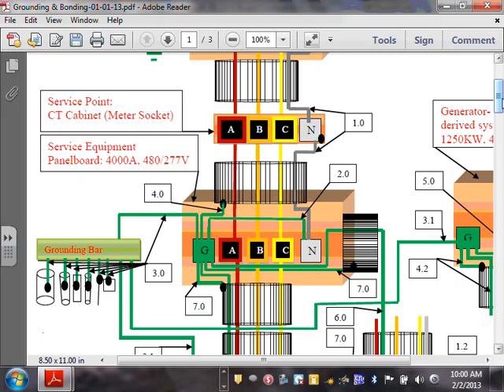And I take my neutral and bond it with that green, till you see that little number 2, and I bond the neutral. You do this at every service if the service is a grounded system. If the service is an ungrounded system, that number 2 does not exist, right? Any comment, any questions about number 2? That's the bread and butter of basically grounding and bonding. You take the neutral and you bond it right to the service. We all know that, right?